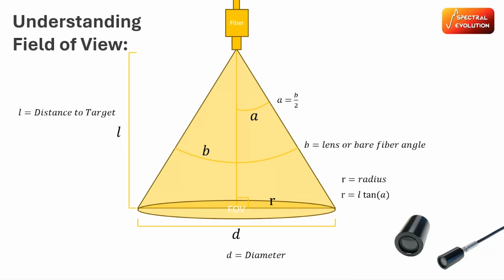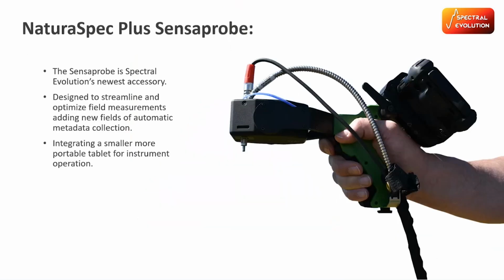different kinds of applications. And so with that, the Sensaprobe has all of our lenses integrated so that it will calculate the field of view based on any degree lens that you're using on the Sensaprobe. And it will quickly adjust its calculation using that distance finder and the angle that it will be at. So the Sensaprobe's obviously our newest accessory. It is designed to be ergonomic and easy to use. In one hand, you can operate the instrument, you can take scans, and you can collect all of that metadata, all with a hand free to do whatever you need to do in the field.